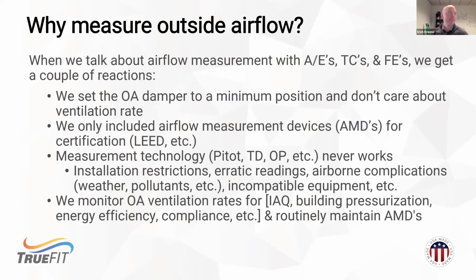before we go into the technology. When we talk to engineers and contractors out there, we ask them about specifically outdoor airflow. We get a few different reactions. Some people just set a minimum damper rate one time at a specific fan rate and say that that's good enough. Typically, they're giving up a lot of system performance and energy savings when they do that.